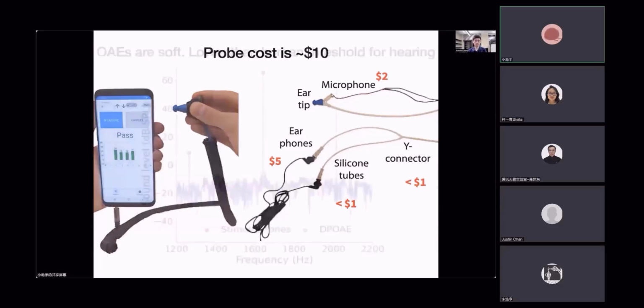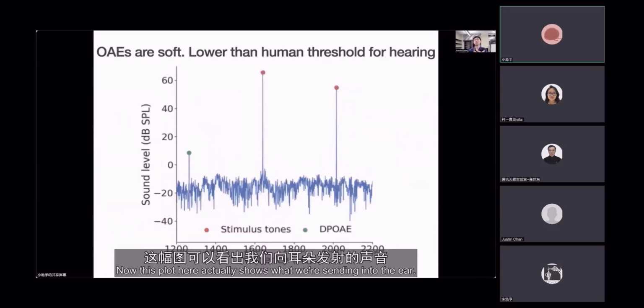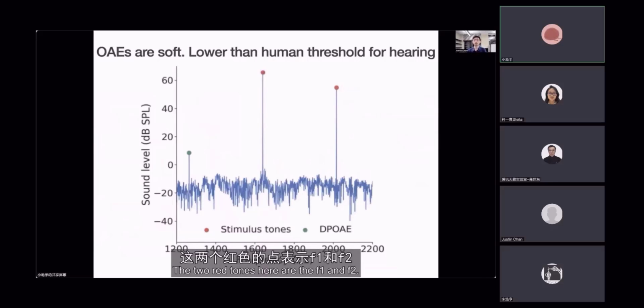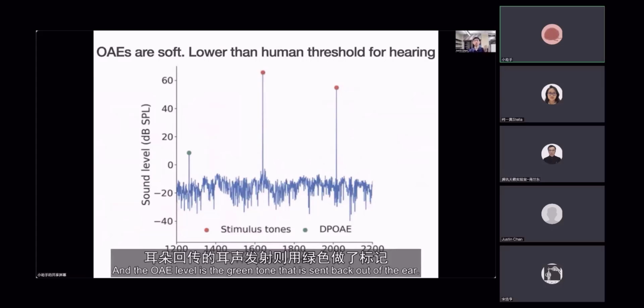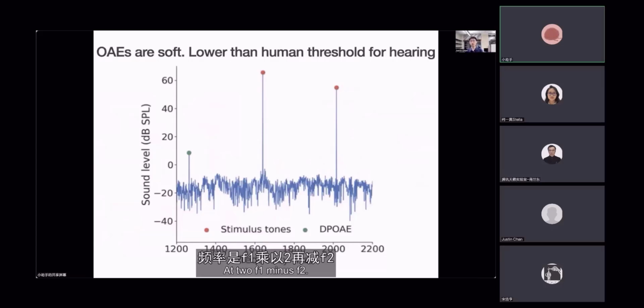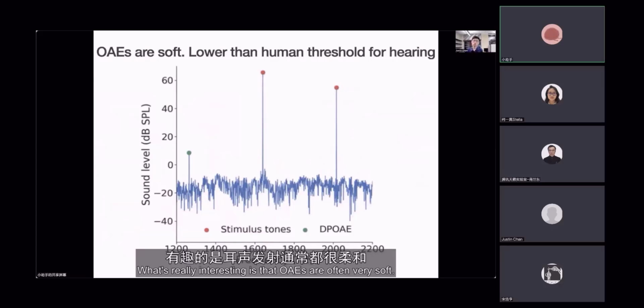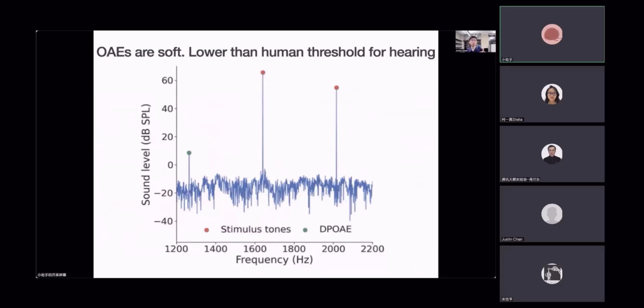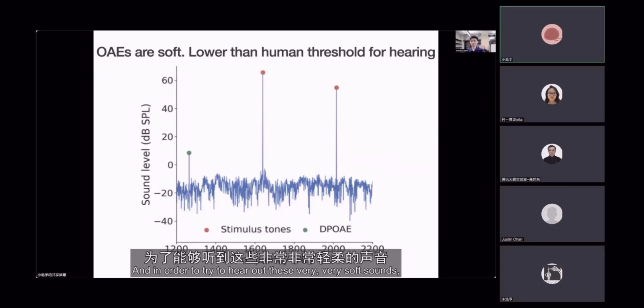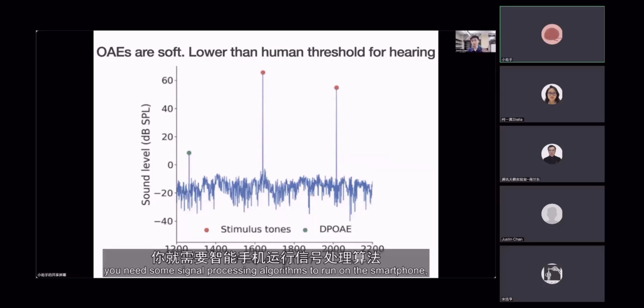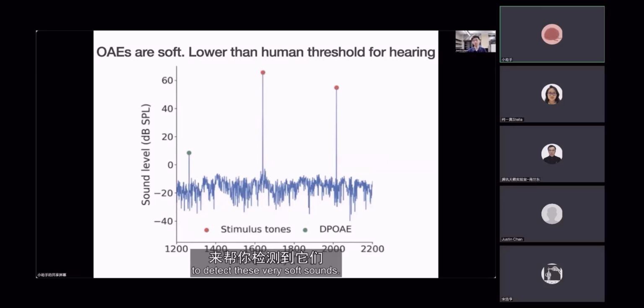And you can set F1 and F2 to like 5 kilohertz if you wanted to test hearing at a slightly higher frequency. Now this plot here actually shows what we're sending into the ear. The two red tones here are the F1 and the F2 stimulus tones. And the OAE level is the green tone that is sent back out of the ear at 2F1 minus F2. What's really interesting is that OAEs are often very soft, and they're often even below the human threshold for hearing, which is 0 dB SPL. Because of that, humans often can't even hear them. And in order to actually tease out these very soft sounds, you need some signal processing algorithms to run on the smartphone to detect them.